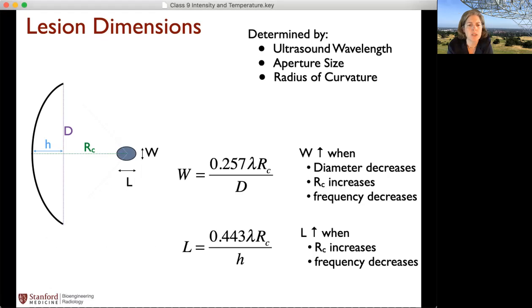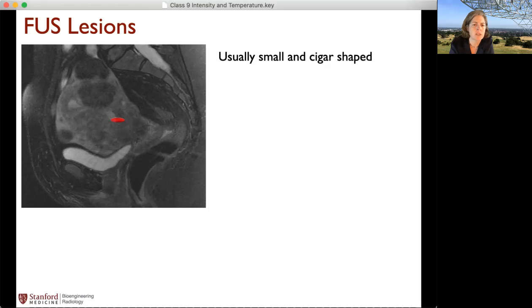Okay, yeah, and we've talked about lesion dimensions as well prior to this. One of the points I wanted to make also is that oftentimes you have, let's say this is a fibroid right here, and the focused transducer is inside the tabletop, and it's focusing to a point deep inside, and then there's that cigar-shaped lesion. And it's small, oftentimes, compared to the area that you want to treat. So if you wanted to get a large volume treated, then you have to do multiple of those. And so this is now showing you a cartoon where we scan around one after another. If each one takes about 20 seconds, and then you have to wait for a minute between them, now maybe you've waited 10 minutes to do something of a small volume like this.